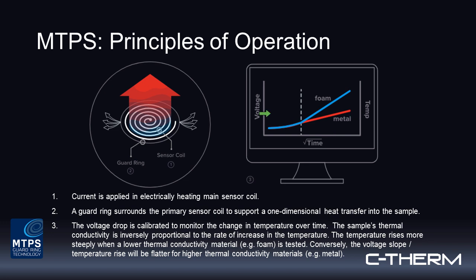We're monitoring the voltage drop on that coil as it's inversely related to the temperature change over time. So it's a calibrated method. We calibrate that voltage drop change to temperature change. And the relationship of that temperature change to the effective thermal conductivity of the material is an inverse relationship. So if we have a really steep rise in a temperature change, we have a really low thermal conductivity material like a foam or insulation. If we have a more negligible rise in temperature change over time, we have a good heat sink material on the sensor, a metal material, a high thermal conductivity, good heat dissipator in contact with the sensor.